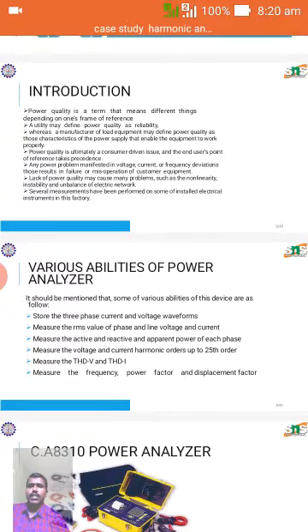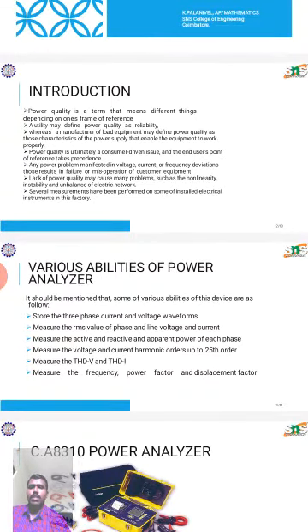Power quality is a term that means different things depending on one's frame of reference. For instance, a utility may define power quality as reliability, whereas a manufacturer of load equipment may define power quality as those characteristics of the power supply that enable the equipment to work properly. These characteristics can be very different for different criteria. Power quality is ultimately a consumer driven issue, and the end user's point of reference takes precedence.